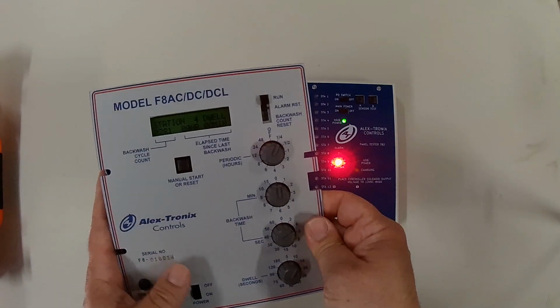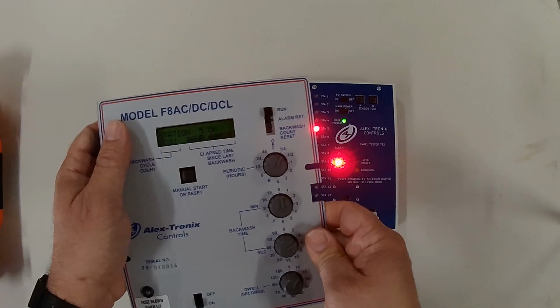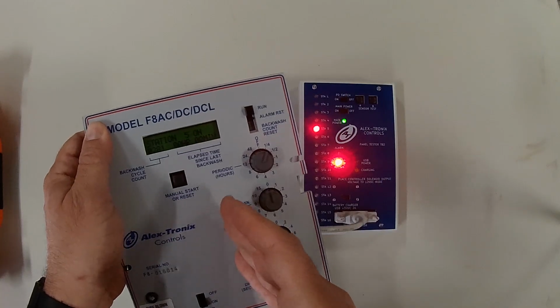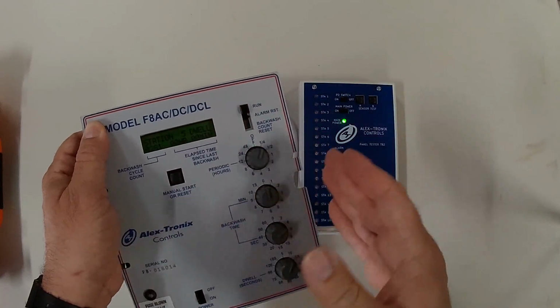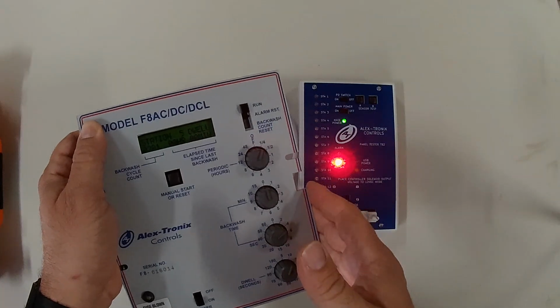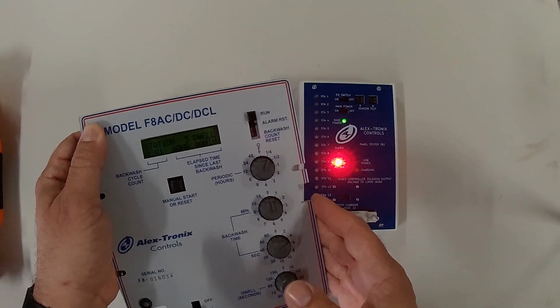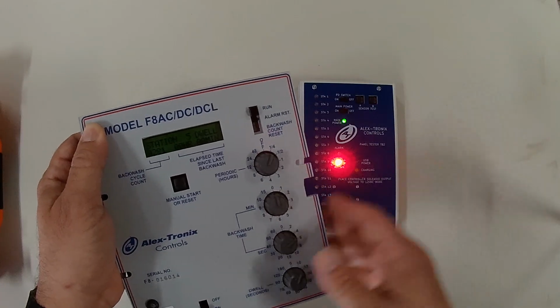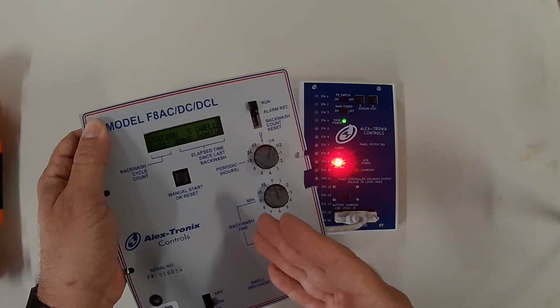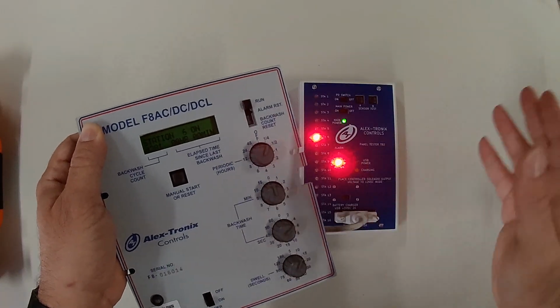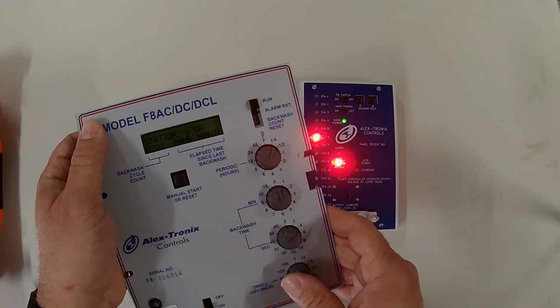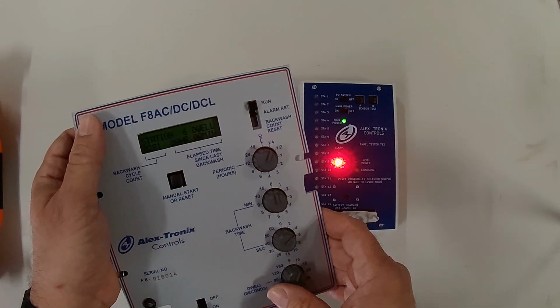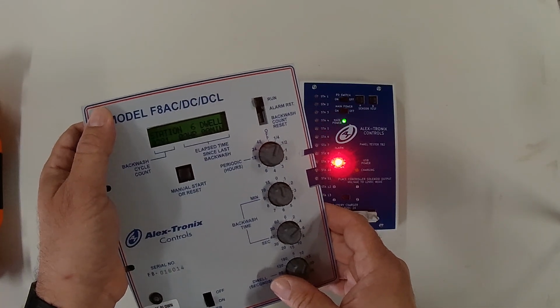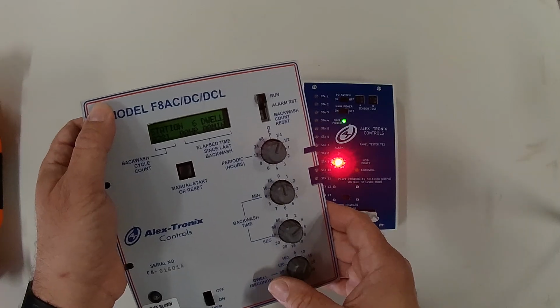But this should really save you some time to know, do I have an actual panel problem? Does this thing need to go back in? Is the problem somewhere else with the filter system? And save you that one extra trip from having to drive back and forward. If you know you've got a bad panel, just go ahead and swap it out there, send the other one in, or it can allow you to readily troubleshoot solenoids or wiring.